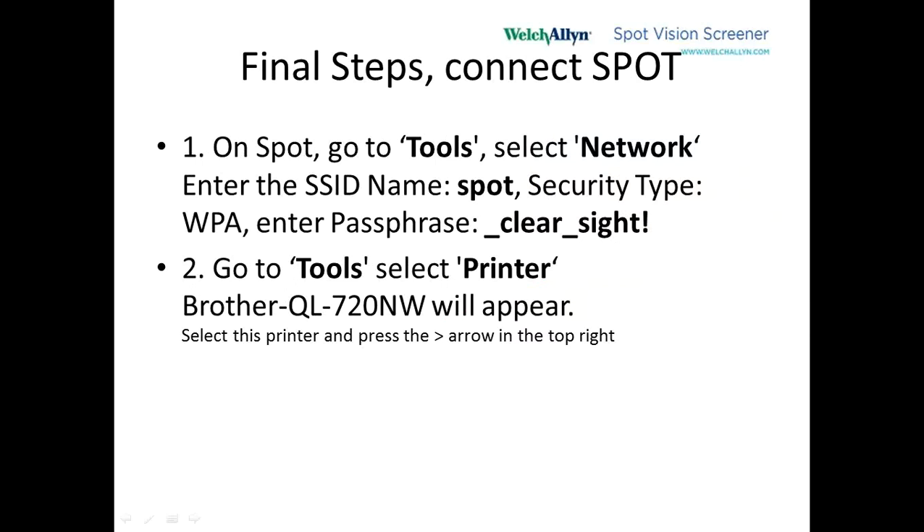Finally, we're going to connect the Spot Vision Screener. Turn it on — that will take about a minute. Then go to Tools and select Network. Under SSID, type the name SPOT like we did before. The security type is WPA, and then the passphrase at the bottom is: underscore clear underscore sight exclamation point. After typing all that in, hit Save. There's usually about a 30-second delay, and then the Spot sees the network.